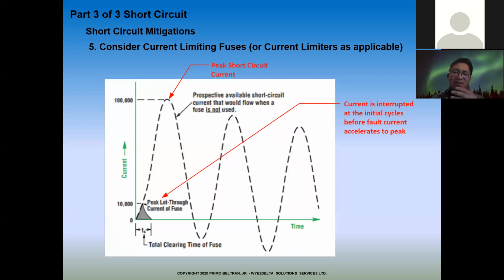So this strategy is sometimes used as a mitigation, as a temporary solution only, because reliability is impacted by it. But as a new design, you can use this. That's why in medium voltage MCCs you'll see a contactor-fuse arrangement, and since they're just operating the motor, it's okay to go with the fuse. The only problem with fuses is that every time one blows, you need a spare.